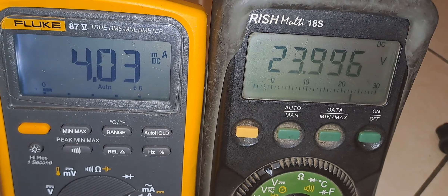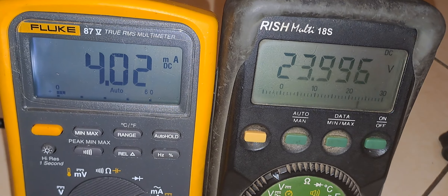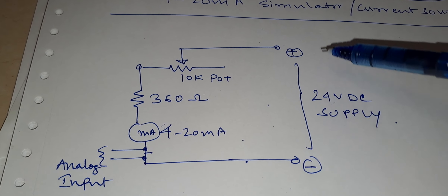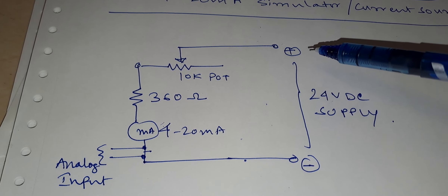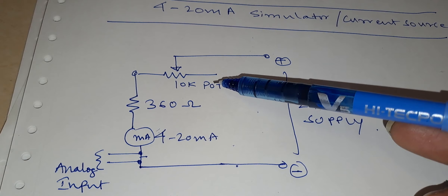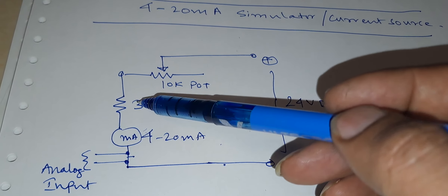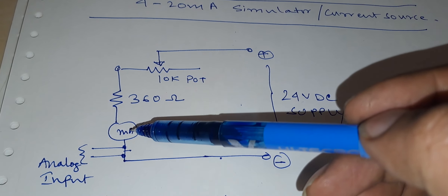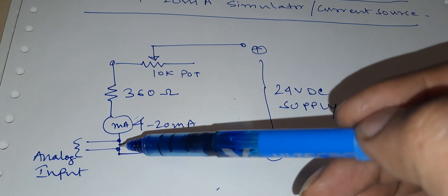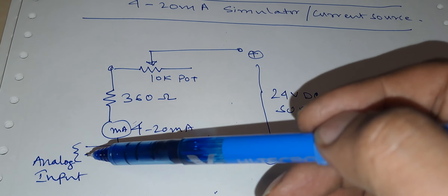This can be achieved with a very simple circuit. Here is the simple circuit diagram for a 4 to 20 mA simulator. This is a 24 volt DC supply, controlled by a 10 kilo ohm potentiometer. The open end of the potentiometer is connected with a 360 ohm resistor and a mA meter for display, and from there it is connected to the analog input card.